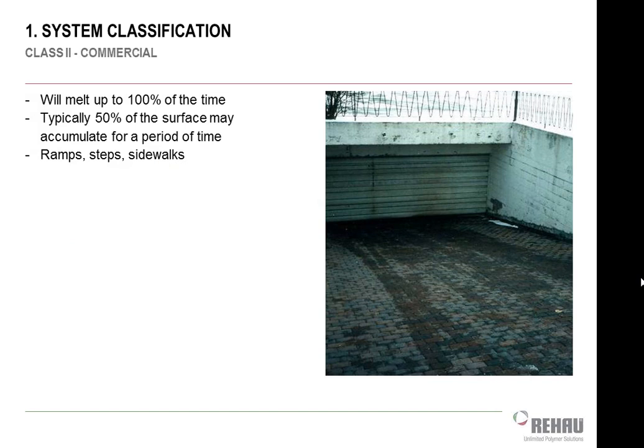Class 2 systems are what we use for typical commercial spaces. So these are going to typically be like this picture shows here, a parking garage ramp, or in front of a senior center or something like that. These are basically sized to be able to handle 100% of the snowfall. So these are going to be a little bit bigger than those Class 1 systems, a little bit bigger in terms of the boiler and GPM capacities, because we want to be able to take care of all the snowfall days of the year.